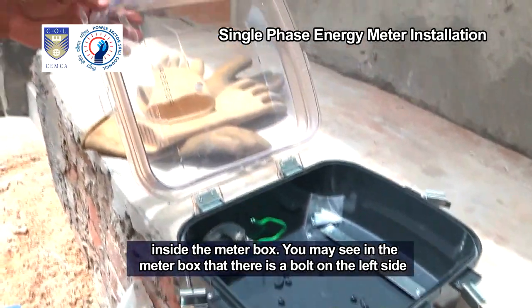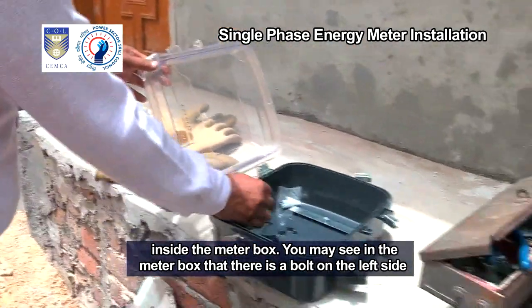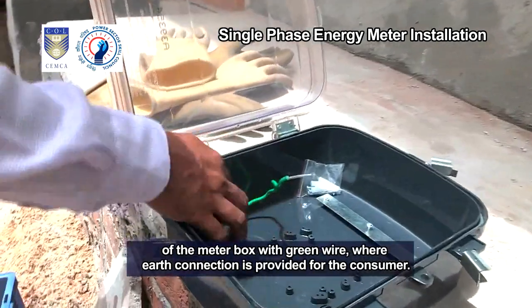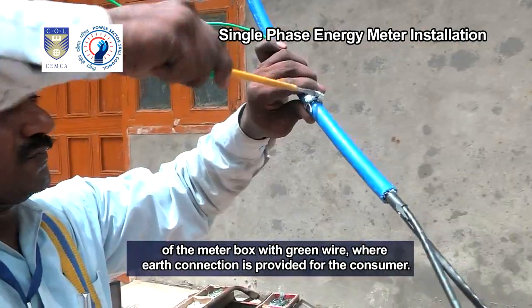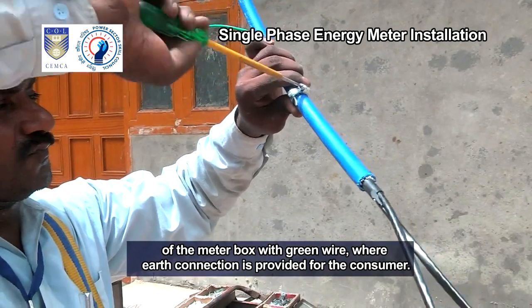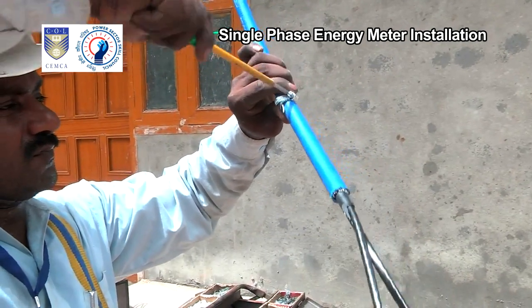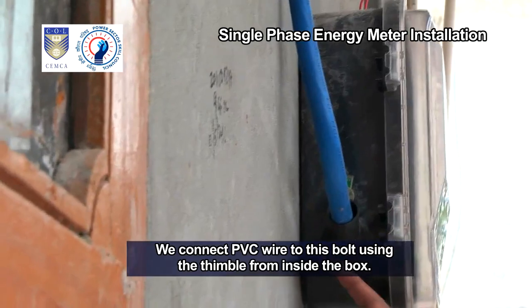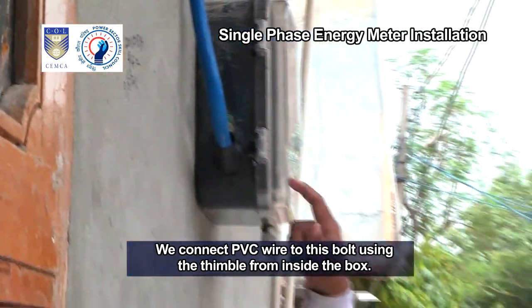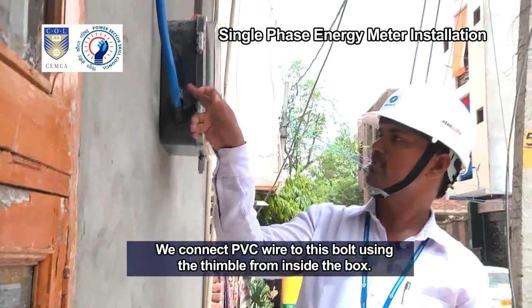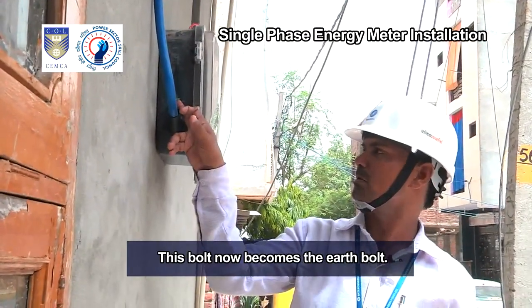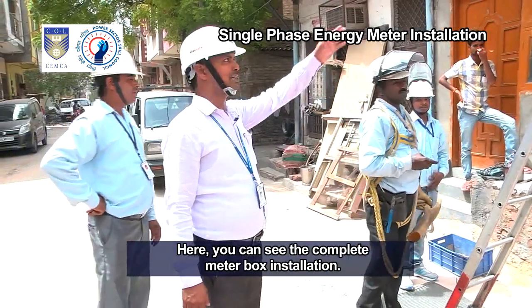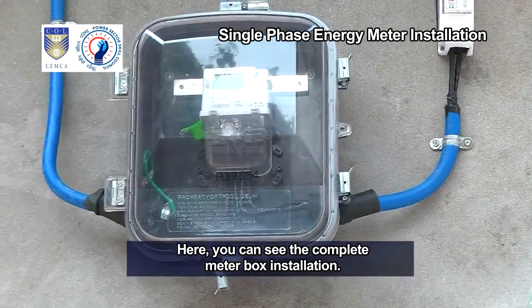You may see in the meter box that there is a bolt on the left side of the meter box with green wire, where the earth connection is provided for the consumer. We connect the PVC wire to this bolt using the thimble from inside the box. This bolt now becomes the earth bolt. Here you can see the complete meter box installation.